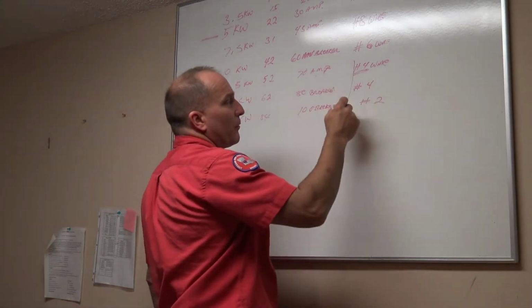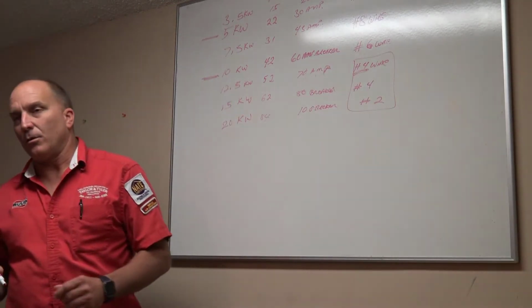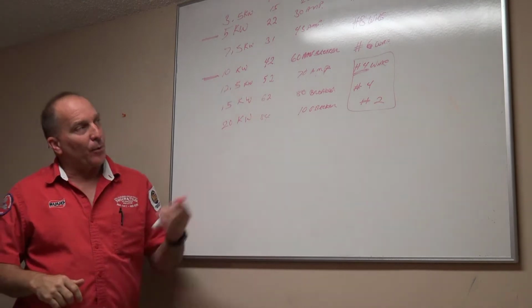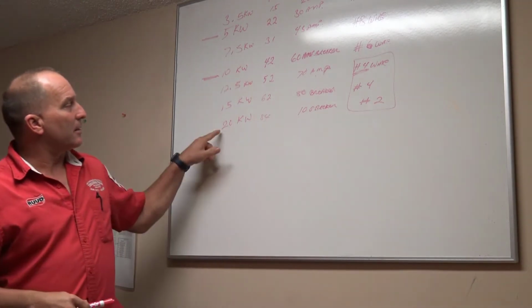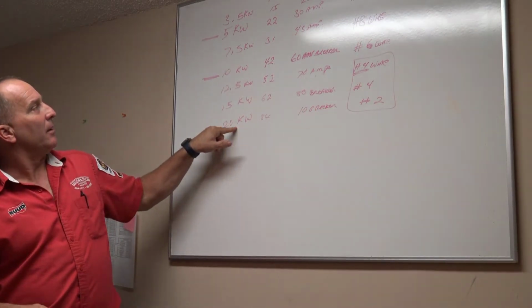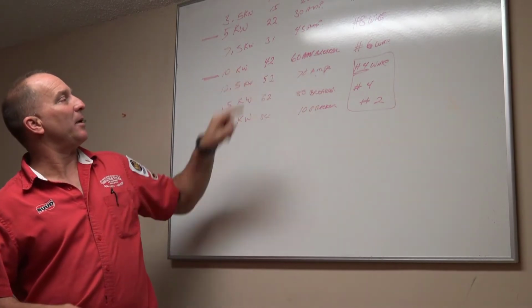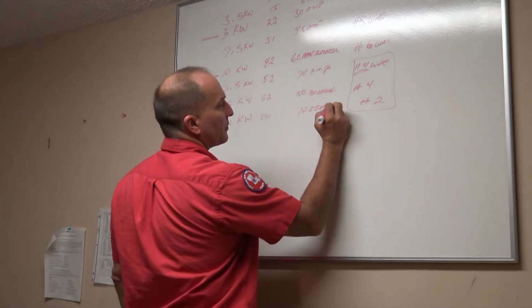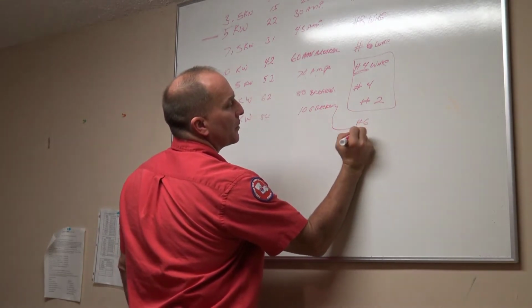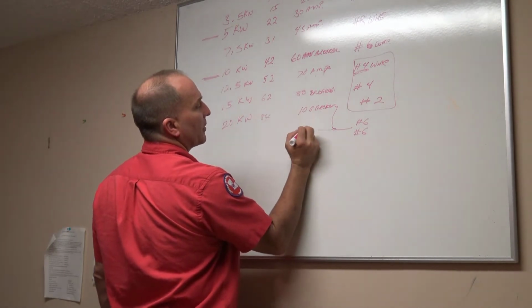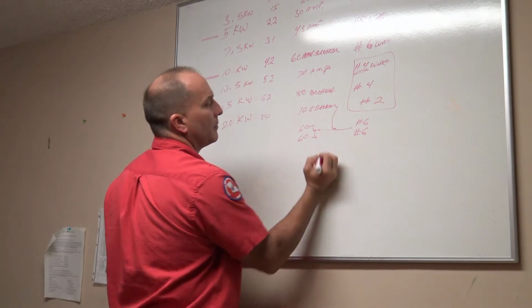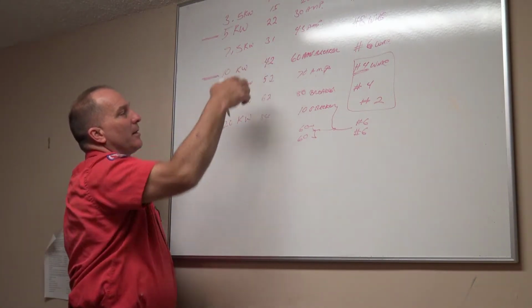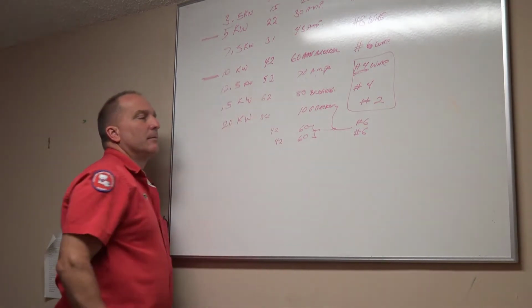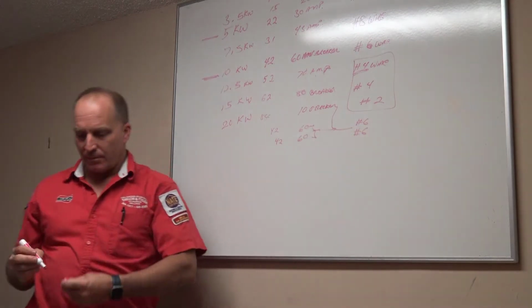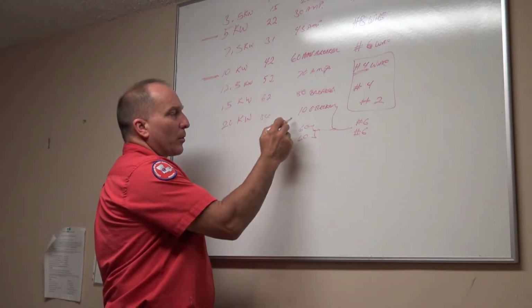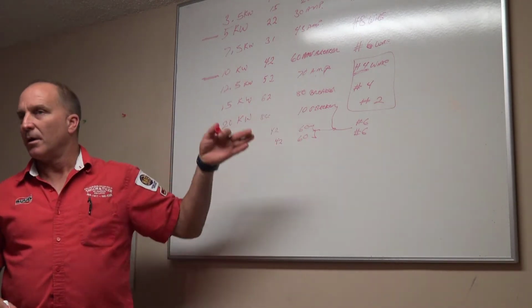Not too often do you see number 4 and number 2 wire run into the air handler. Not too often do you see that. And the reason is because the price of those wires is just high. So instead of running a number 2 wire into a 20 kW heat system, they just go 2 number 6 wires for 2 10 kW heat systems. So this one here now becomes number 6 with 2 60 amp breakers. Now we have each holding 10 kW at 42 and 42. Now I have 20 kW heat on 2 number 6 wires, and they're separated. There is not any kind of jumper over or anything like that, okay? It's just 2 separate wires, 2 disconnects, everything.